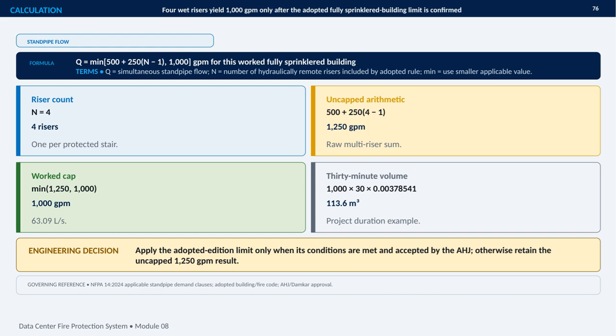The engineering decision is important. Apply the 1000 GPM cap only when the adopted-edition conditions are satisfied and accepted by the authority having jurisdiction. Otherwise, retain the uncapped 1250 GPM result. The governing references are NFPA 14, the adopted Building and Fire Code, and AHJ/Damkar approval.